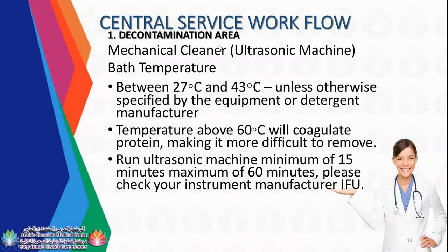So your mechanical cleaner, guys, should have the temperature set to 27 degrees Celsius to 43 degrees Celsius. Actually, you can operate the mechanical cleaner without setting the temperature to that range, even at zero or as normal. As it is, it can be used.